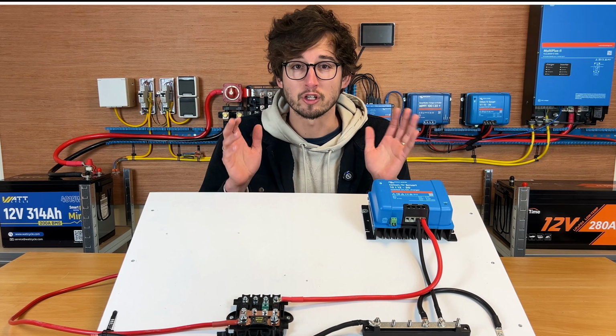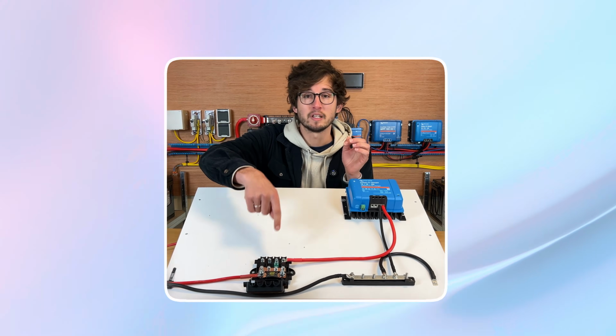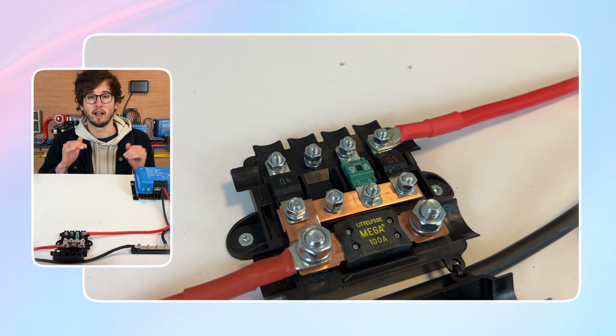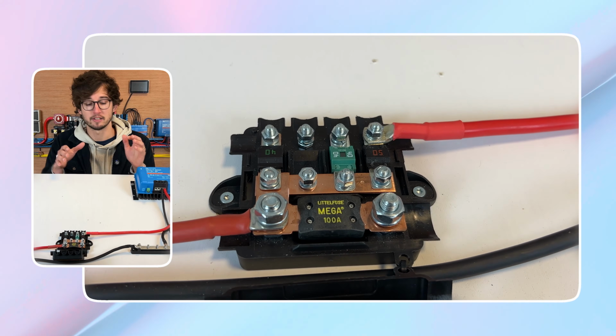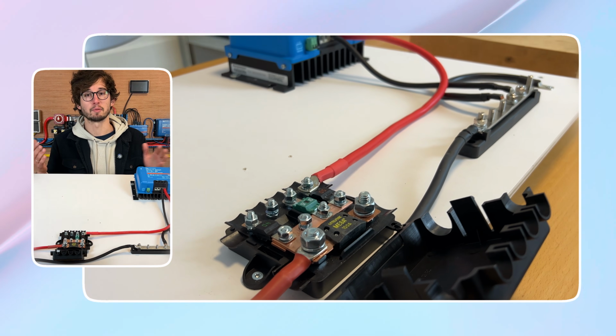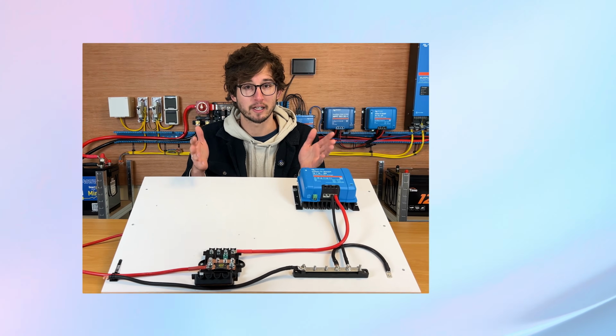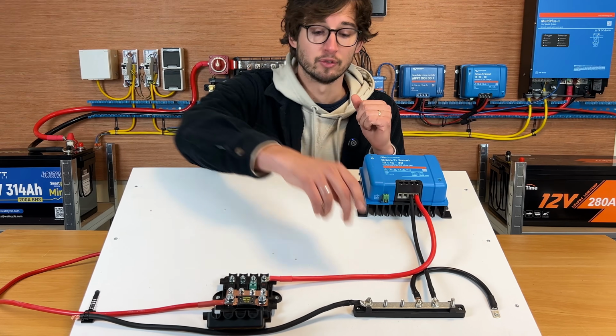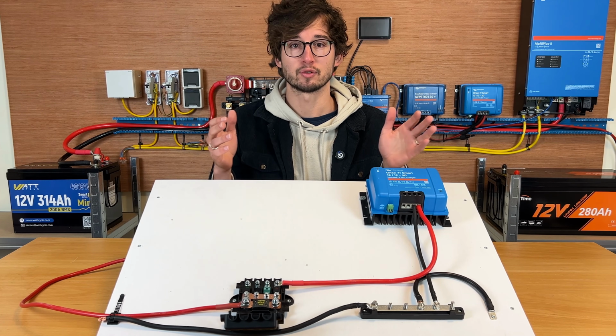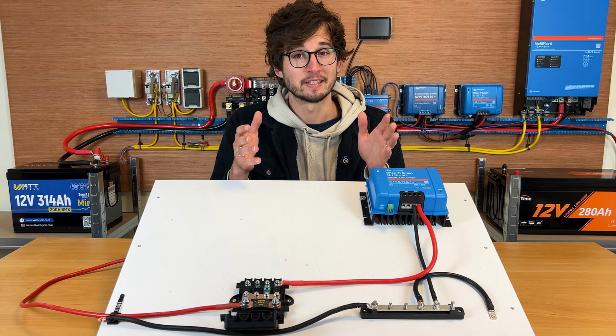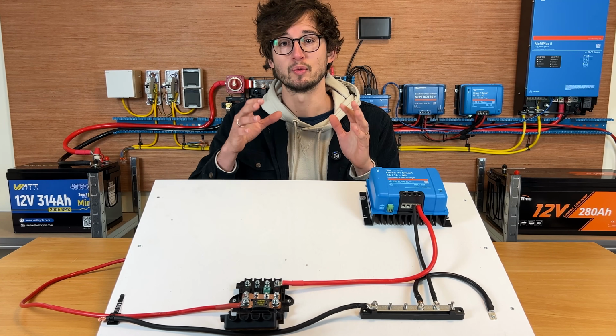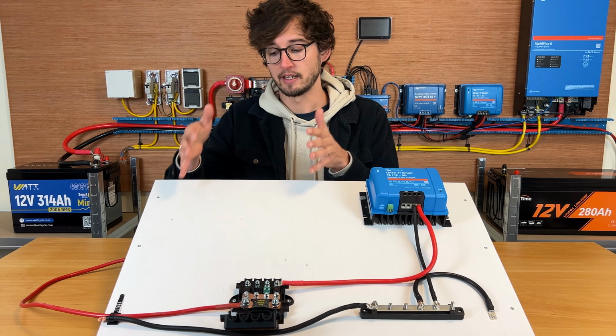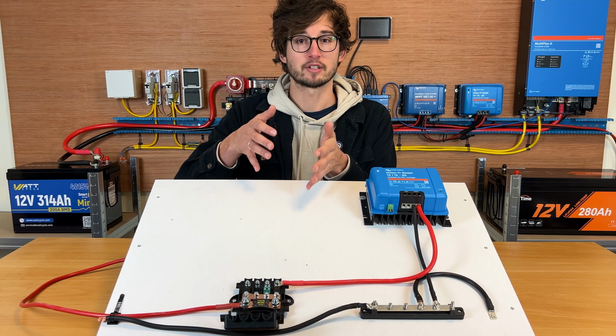So this is the first alternative, and this is called a Midi Mega fuse holder. With this you can directly place your lugs onto the fuse without cutting your cables in half and adding extra connections. You would still need, of course, a negative bus bar to connect your negative lugs, and as you can see, this is also way more compact than the individual bus bar with separate fuses.